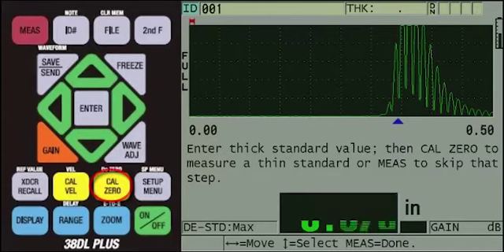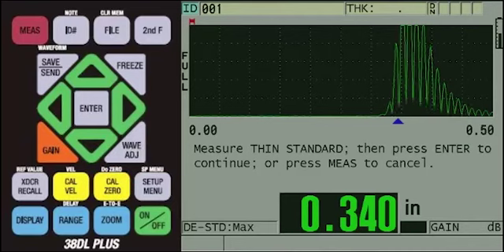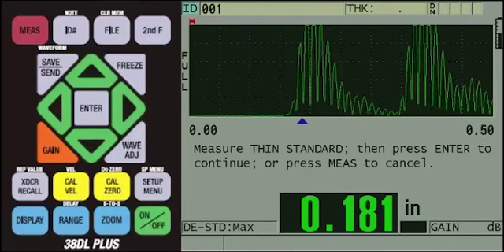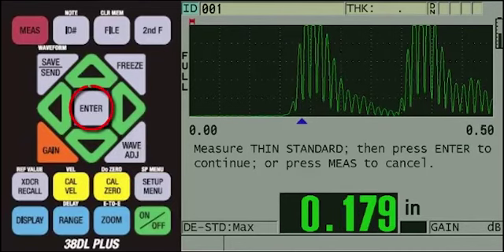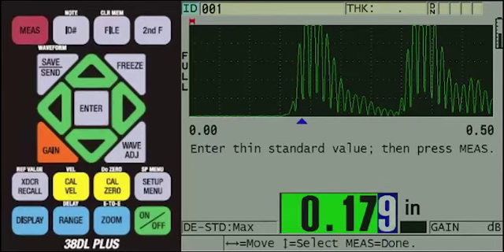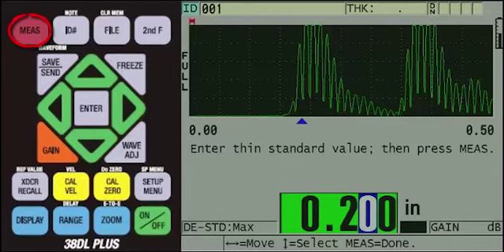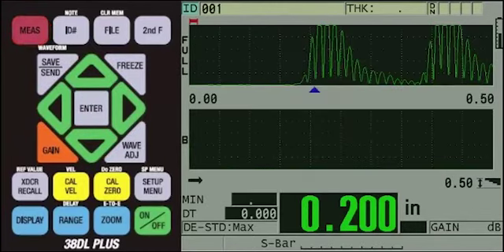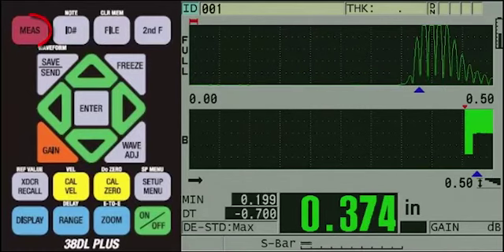We can then press the yellow Cal-0 key and then position the buggy onto the thin area of the plate. Once the reading is steady, press the Enter key. Then we will use the arrow keys to change the value to 0.200 inches or 5.08 millimeters. Then press the red Measure key. Place the transducer and buggy setup on the right side of the aluminum plate, then press the red Measure key to reset the captured minimum and the distance traveled. Then you can begin scanning the plate.